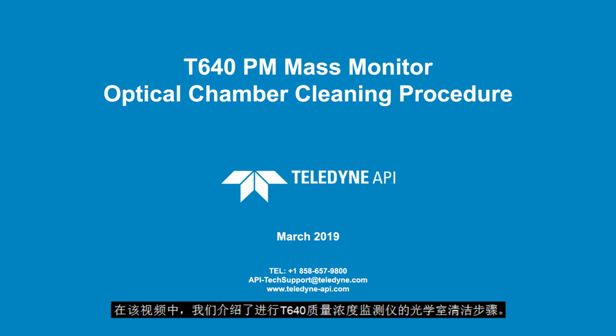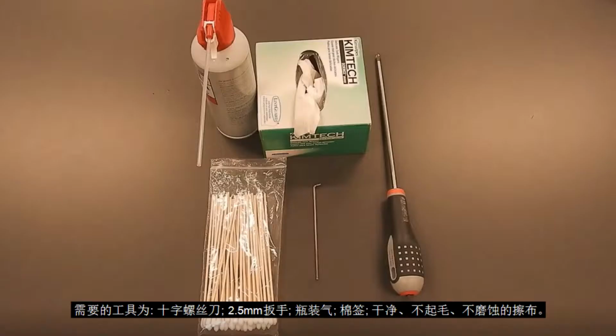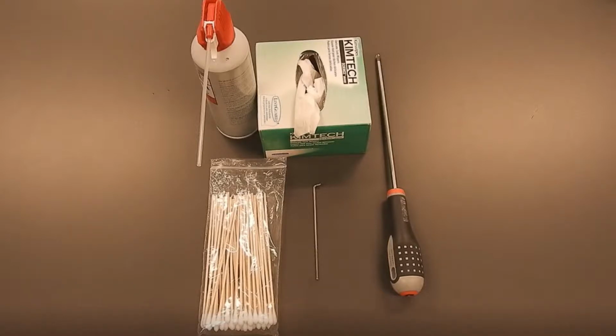In this video, we will be demonstrating how to perform the optical chamber cleaning for a T640 PM mass monitor. This procedure is recommended every 6 months or more, depending on operating conditions or if there is any difficulty performing a calibration. Items needed include a Phillips head screwdriver, a 2.5mm Allen wrench, canned air, cotton swabs, and dry, lint-free, non-abrasive wipes.